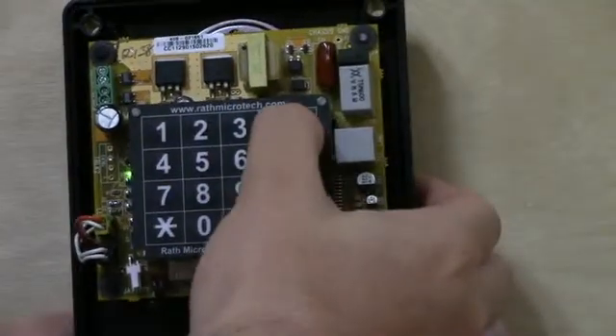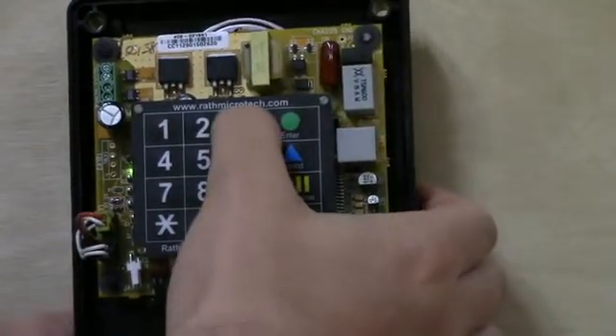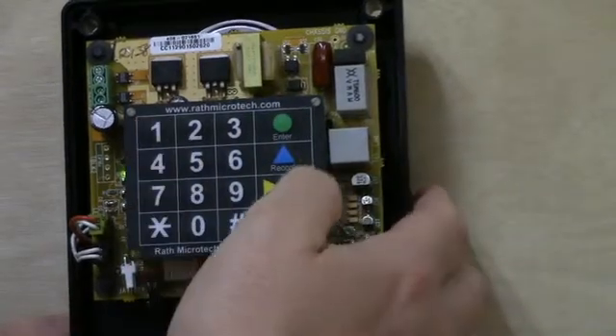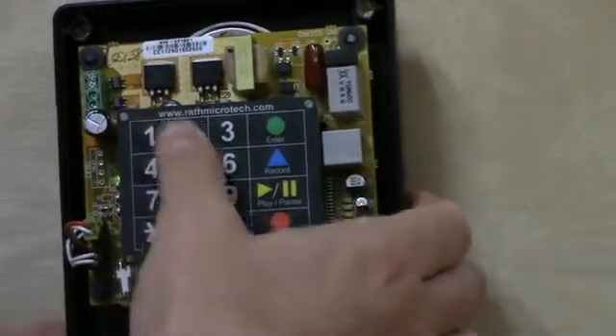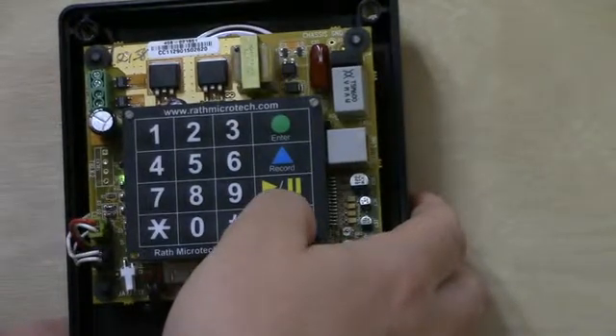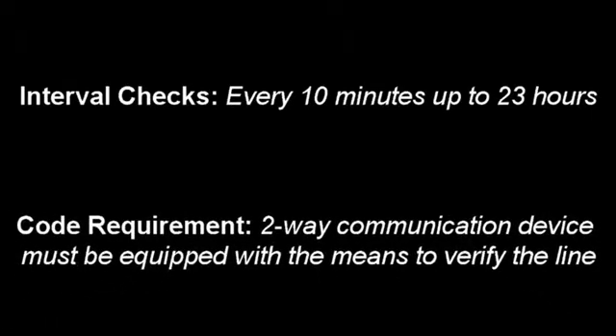Step 1. You will install a 2100 series phone in the elevator. These phones can be equipped right out of the box to meet all code requirements. Perform your standard programming of the phone. You can also program the phone with the interval you want it to check the phone line — every 10 minutes all the way up to 23 hours. The code states that the 2-way communication device be equipped with the means to verify the line.